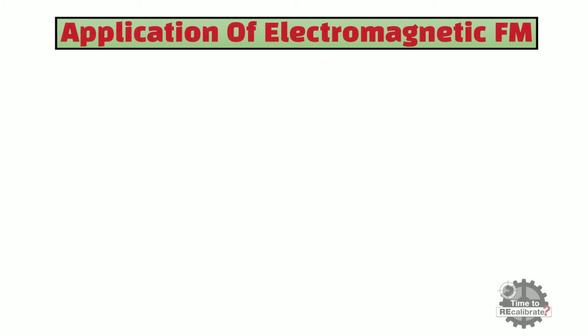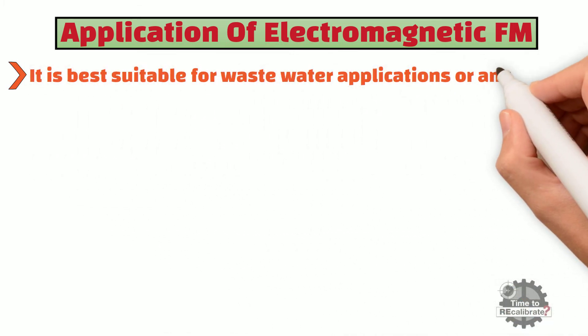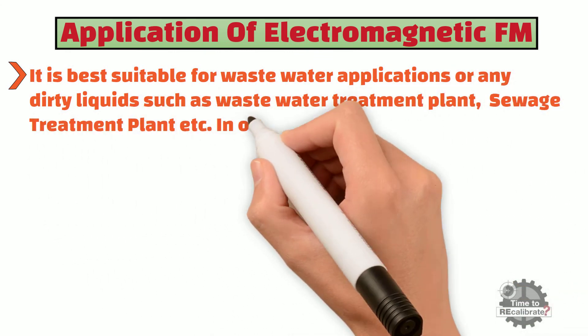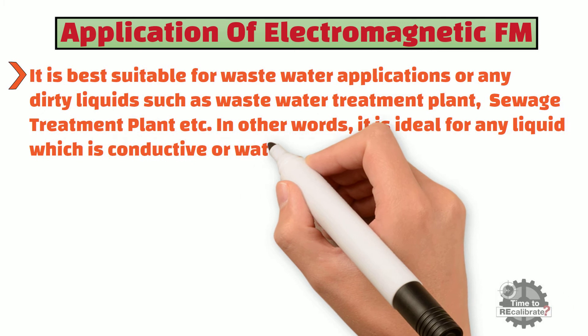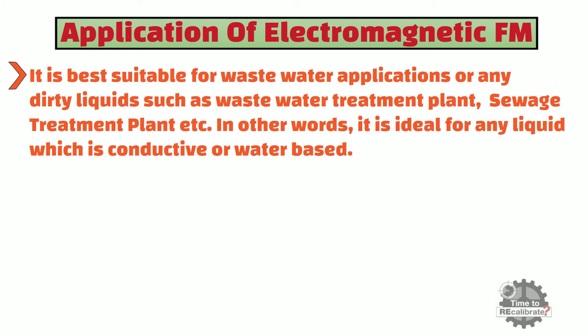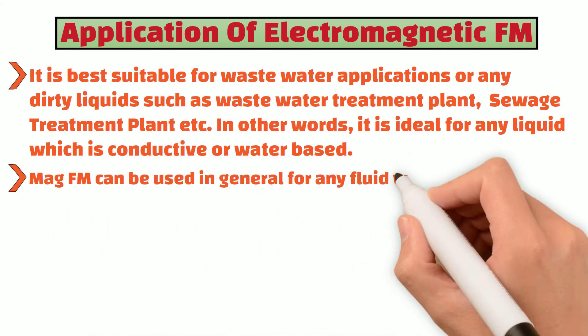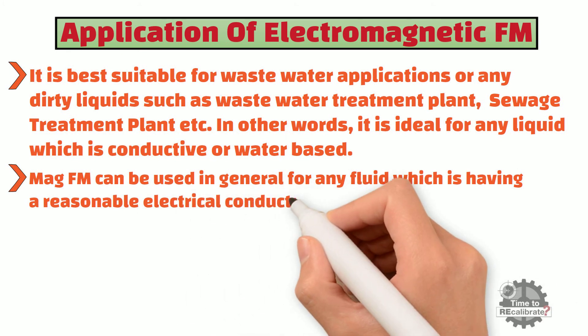Electromagnetic flowmeters are best suited for wastewater applications or any dirty liquids, such as wastewater treatment plants and sewage treatment plants. In other words, they are ideal for any liquid that is conductive or water-based. Mag flowmeters can be used for any fluid having a reasonable electrical conductivity above 10 microsiemens per centimeter.